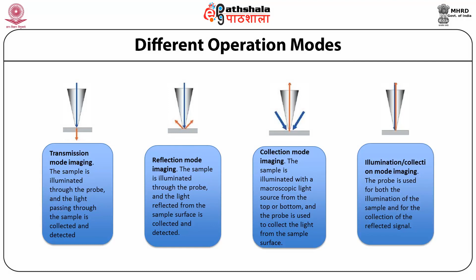Let us discuss different operational modes in the case of NSOM. The light is illuminated in various modes using NSOM. These are as follows. In transmission mode imaging, the sample is illuminated through the probe and the light passing through the sample is collected and detected. In reflection mode imaging, the sample is illuminated through the probe and the light reflected from the sample surface is collected and detected. In collection mode imaging, the sample is illuminated with a macroscopic light source from the top or bottom and the probe is used to collect the light from the sample surface. In illumination/collection mode imaging, the probe is used for both the illumination of the sample and for the collection of the reflected signal.